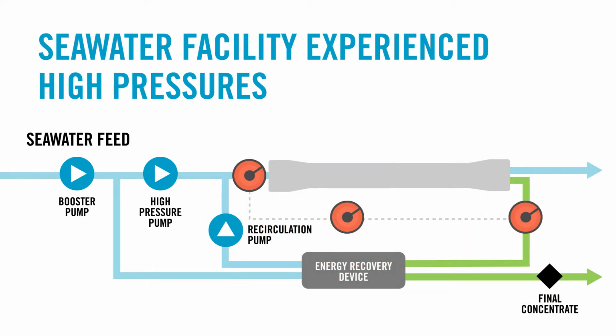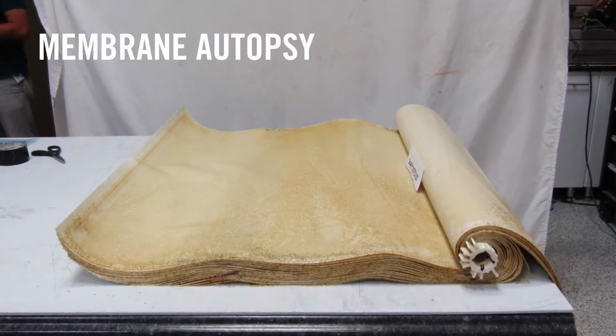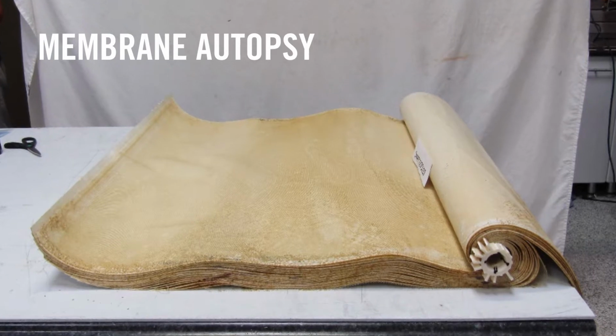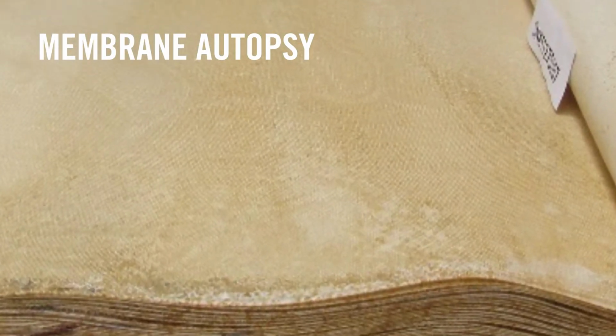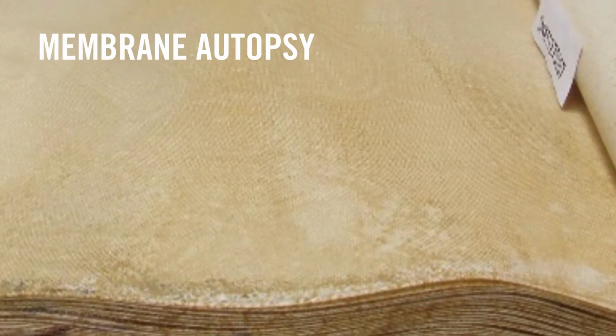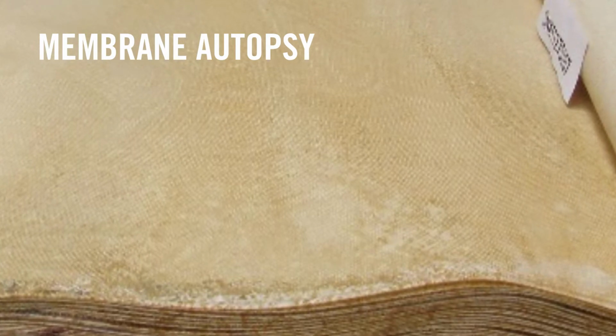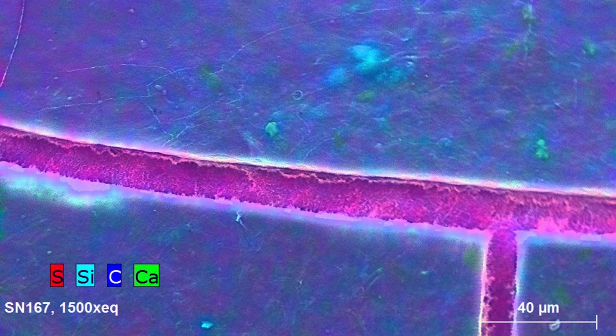Several elements were collected, autopsied, and full element cleaning studies were conducted. Here we have the unclean membrane surface. The membrane is covered in a tan gelatinous material that was determined to be organic fouling. To look at the spatial distribution of the foulant on the membrane surface, we use chromatic elemental imaging.